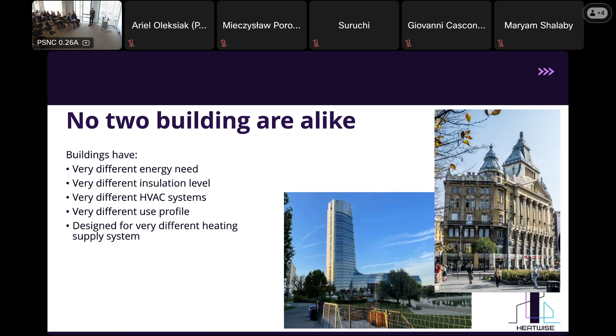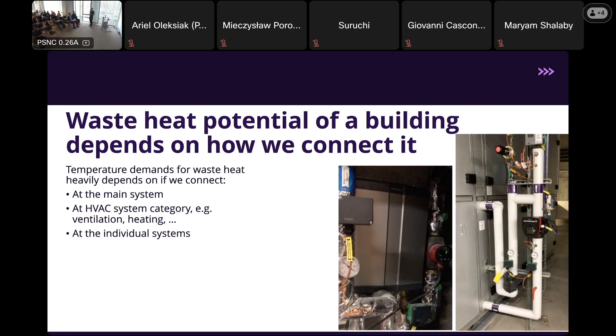When we look at the waste heat potential of buildings, it depends on how we connect it. There are different places in the building where we can connect the waste heat. We can go at the main system, that would be the easiest, where the district heating comes into the building or where you have your boiler. If we connect there, it's very easy, not much plumbing. But we might also be able to do special plumbing for all the HVAC system categories: the ventilation systems, the heating systems, domestic hot water. Or we could actually attack the individual systems, right here at the heat exchanger for domestic hot water, or right here at the heating surface for the ventilation system. And that gives us different possibilities of reusing heat with lower temperatures.